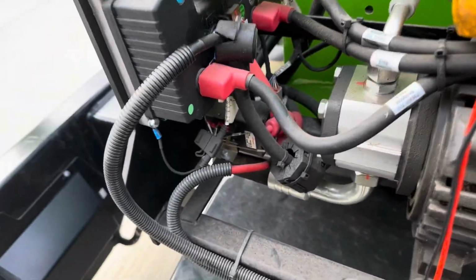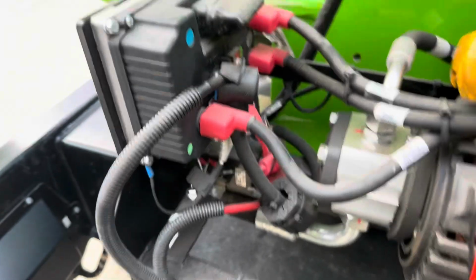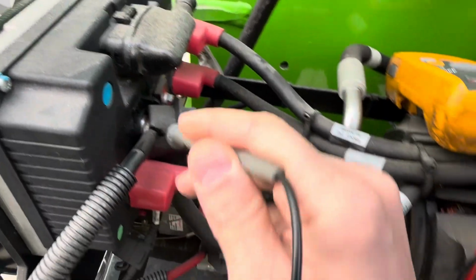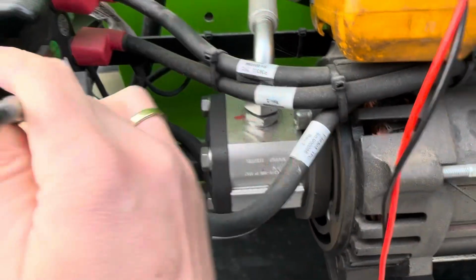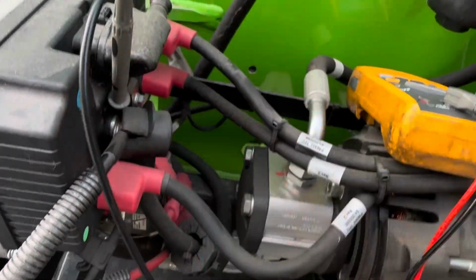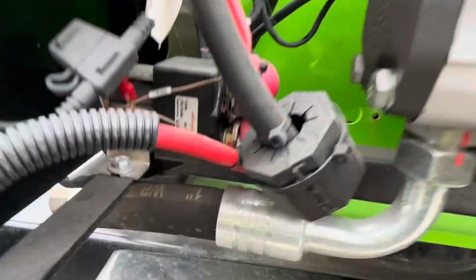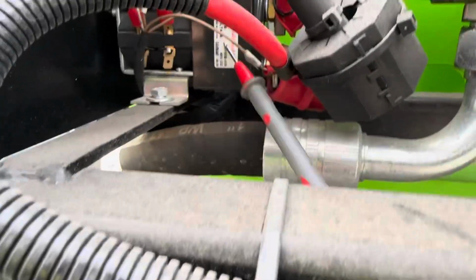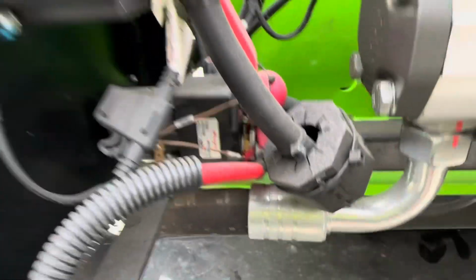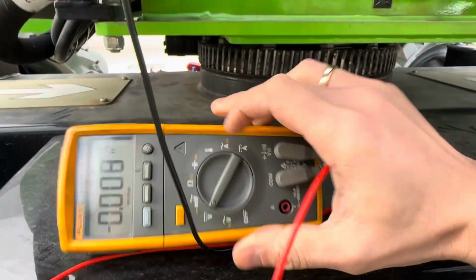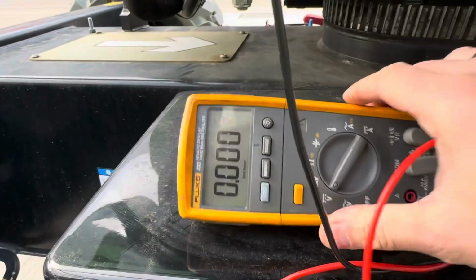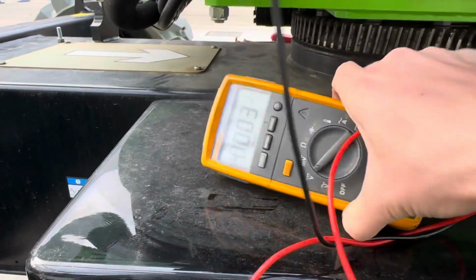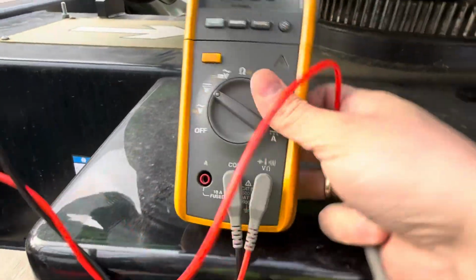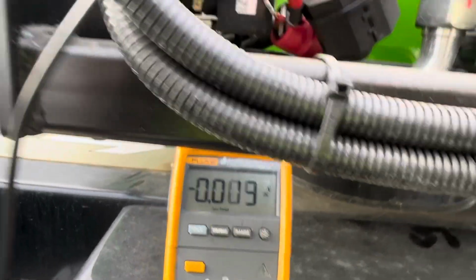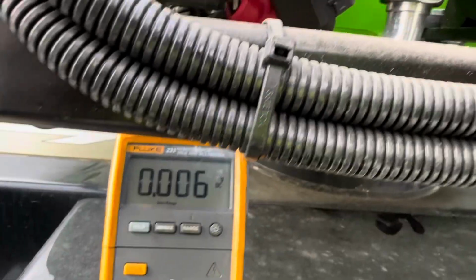The best place to check the 48 volt supply would be the motor controller. We know it has a ground here, and the positive always comes to this 48 volt contactor. So if you measure on the contactor supply side, we should have a 48 volt feed, or whatever the battery voltage is. Okay, let's put on a stand.